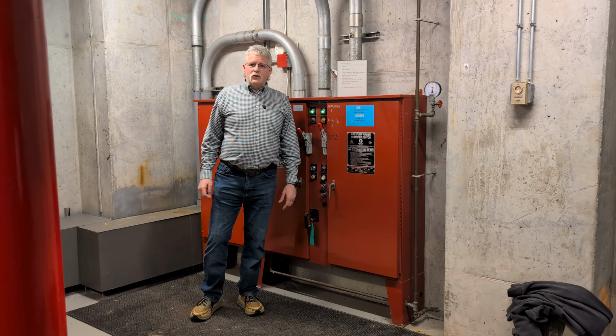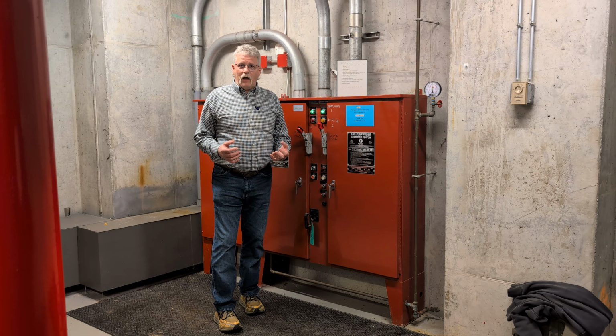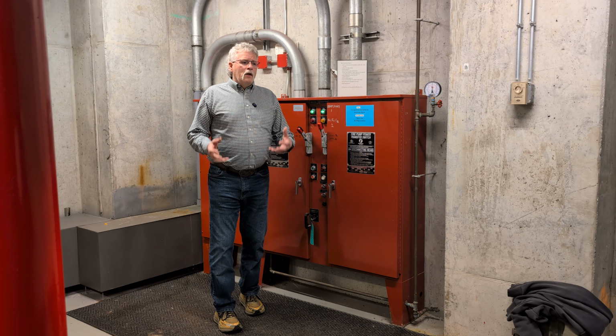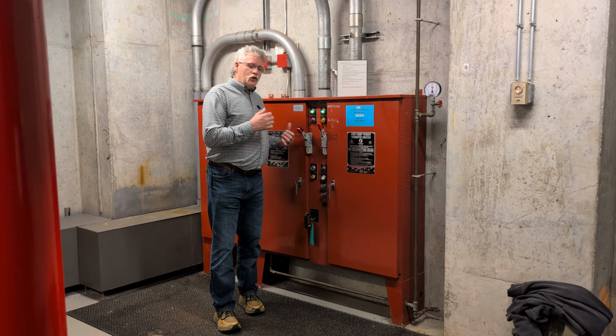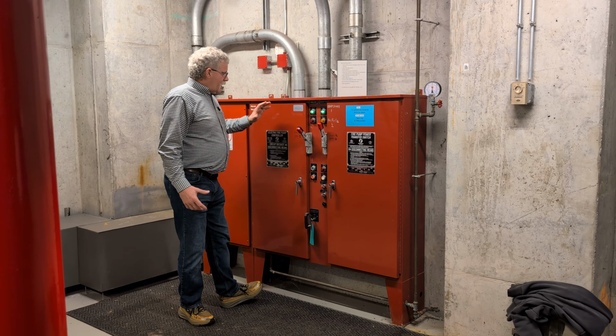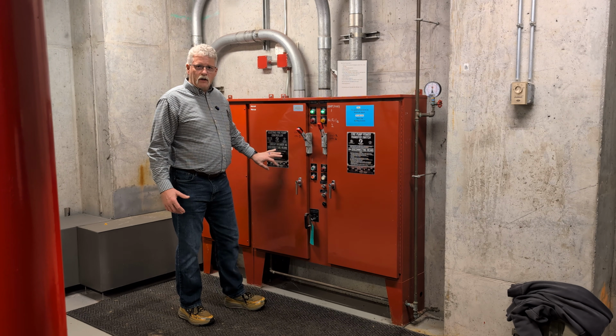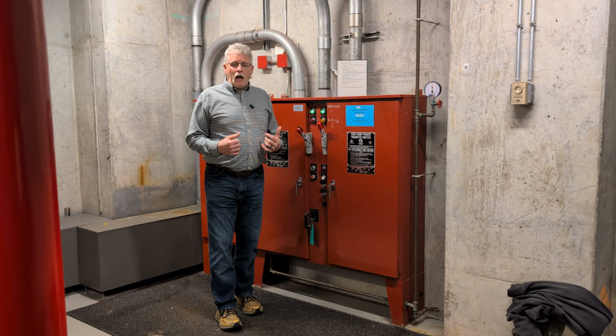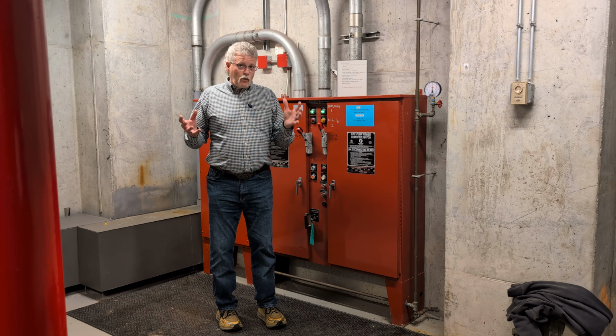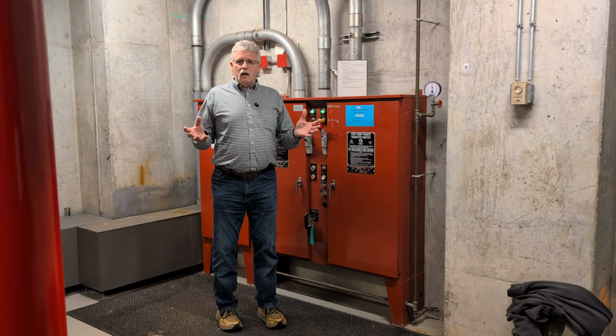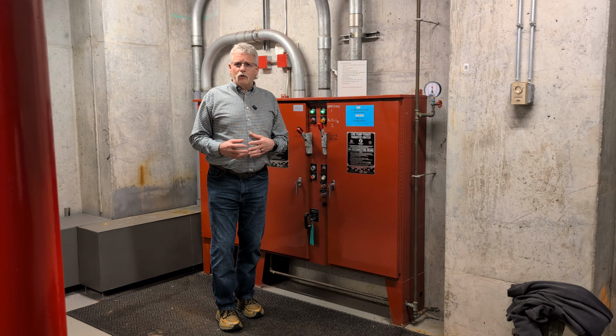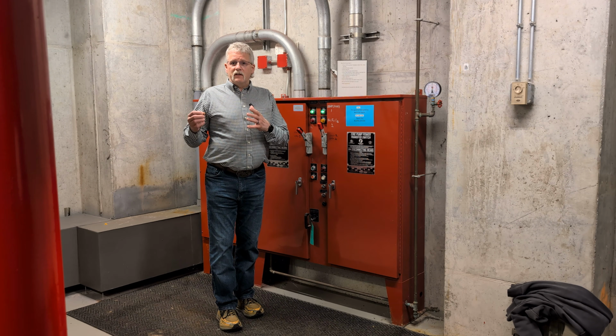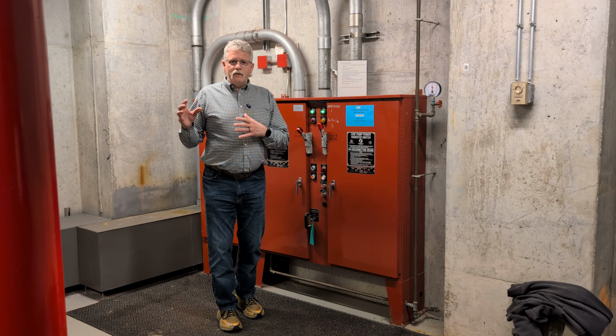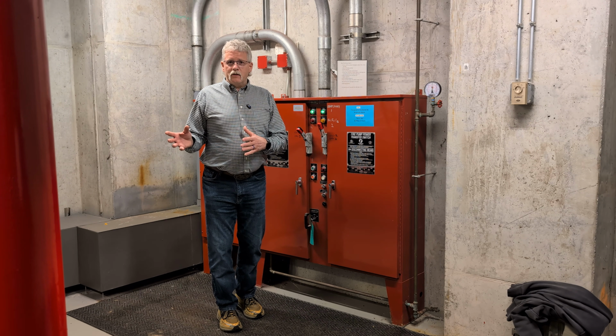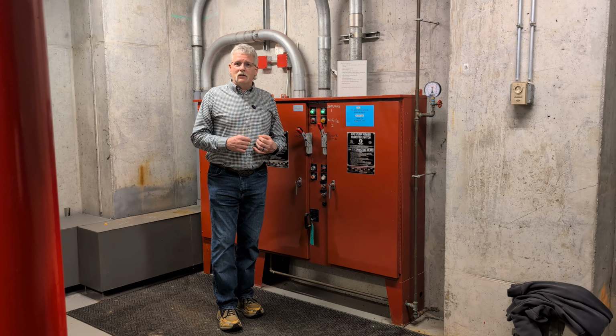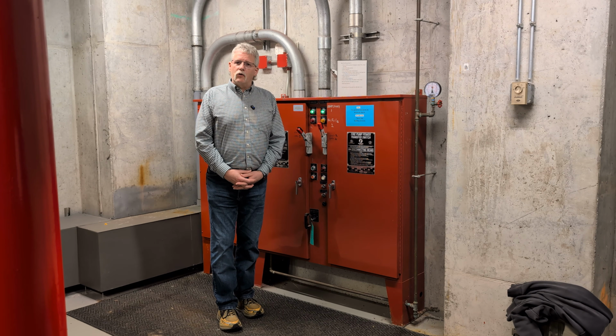So one of the first questions that we received was the requirements for a disconnecting means and overcurrent protective devices for an electric-driven fire pump. These disconnecting means are required, and they're usually found in the fire pump controller as we have here. It has a combination disconnecting means, and it also has a circuit breaker which acts as the overcurrent protective device. These are sized much differently than you would have a feeder panel that maybe would be for receptacles and lighting in a commercial building on a floor. These are sized according to the locked rotor current of the fire pump, and they are designed such that they will hold all of the locked rotor current so that the fire pump will not stop until a catastrophic failure has happened. So it's very important that these are properly installed and that they are properly sized according to the electrical code being enforced at that time.